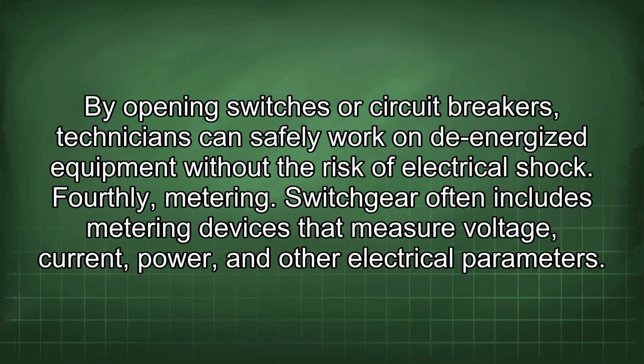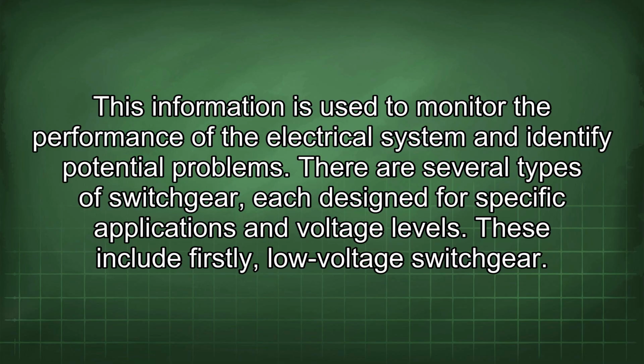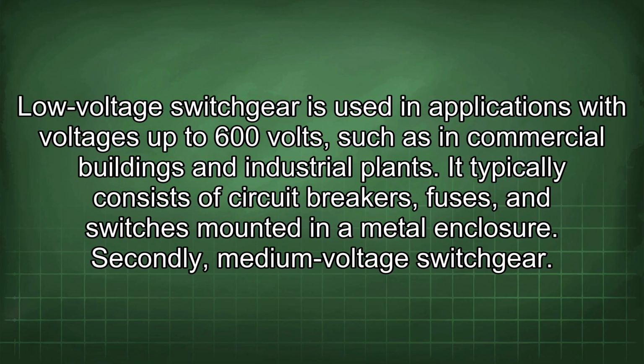Fourthly, metering. Switchgear often includes metering devices that measure voltage, current, power, and other electrical parameters. This information is used to monitor the performance of the electrical system and identify potential problems. There are several types of switchgear, each designed for specific applications and voltage levels. These include firstly low-voltage switchgear. Low-voltage switchgear is used in applications with voltages up to 600 volts, such as in commercial buildings and industrial plants.